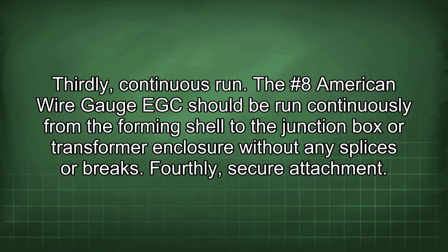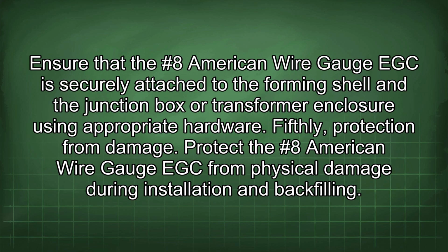Thirdly, continuous run. The #8 American wire gauge EGC should be run continuously from the forming shell to the junction box or transformer enclosure without any splices or breaks. Fourthly, secure attachment. Ensure that the #8 American wire gauge EGC is securely attached to the forming shell and the junction box or transformer enclosure using appropriate hardware.